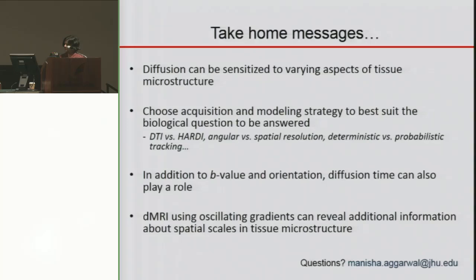It does cause heating of the gradients, and we've also ended up burning the gradients sometimes. But what we can do is, because these scans are at different frequencies, they are a little bit longer than the conventional DTI scans. So we do see motion or displacement of images across different frequencies. This could be because of vibration or field drift or even the sample moving because the gradients are really strong. So what I typically do is just use a simple rigid registration between images across different frequencies so that when we generate a frequency-dependent map, it's all in the same spatial space.